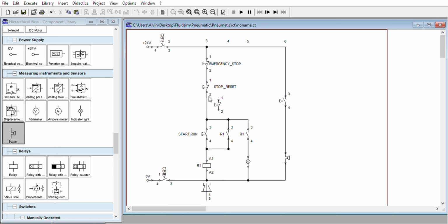So we'll remove this one, series. So if you are going to turn off a circuit, the emergency stop is normally closed. So this is the emergency stop connection. This is the emergency stop connection. They are in series with the coil.